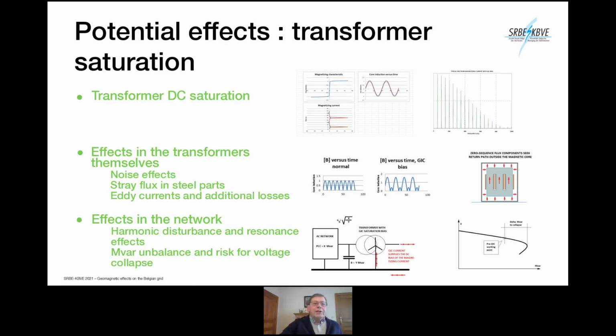What are the potential effects of geomagnetic currents? There is only one effect. It's the saturation of transformers by the DC current. And saturation has one effect. You see on the top figure at the left, with the magnetizing characteristic. In normal operation, the flux is symmetrical around zero, and you get a symmetrical magnetizing current.